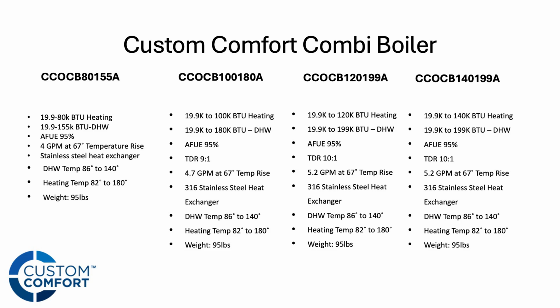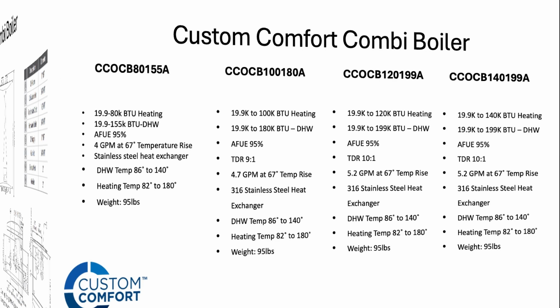Your output temperatures are going to be the same across the 4 different models. On the 100, 180, you're looking at a 9-to-1 turn down ratio, and the 120, 199 and 140, 199 are going to have a 10-to-1 turn down ratio. So these things are going to modulate to help with the efficiency. They're going to handle small zones up to large zones, and when the whole house is calling for heat and/or a large domestic hot water demand, they're going to modulate to meet whatever needs are out there. All these are super light at 95 pounds a piece. And that's kind of a quick rundown here on the combi boilers.